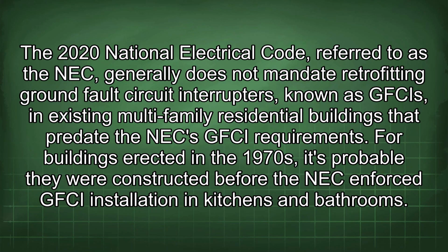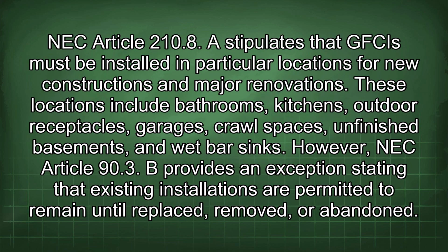The 2020 National Electrical Code, referred to as the NEC, generally does not mandate retrofitting ground fault circuit interrupters, known as GFCIs, in existing multifamily residential buildings that predate the NEC GFCI requirements. For buildings erected in the 1970s, it's probable they were constructed before the NEC enforced GFCI installation in kitchens and bathrooms. NEC Article 210.8 stipulates that GFCIs must be installed in particular locations for new constructions and major renovations.